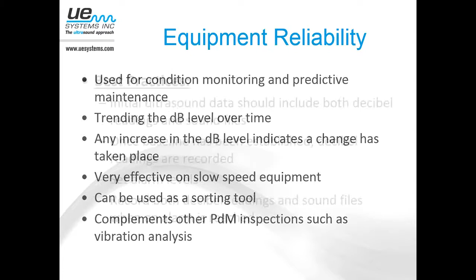Some best practices on equipment reliability. Initial, in other words, baseline readings should always include a decibel and a sound file if your instrument has the ability to record sound files. Very, very important.